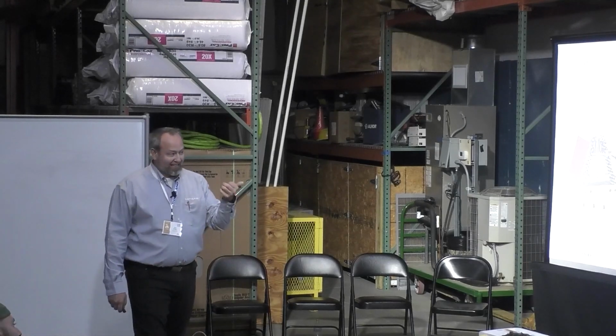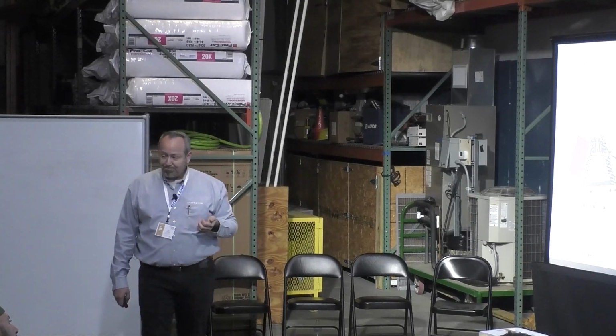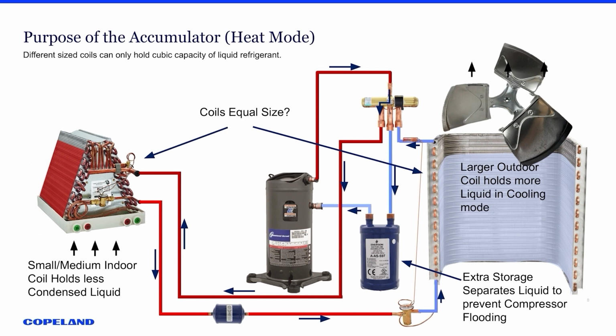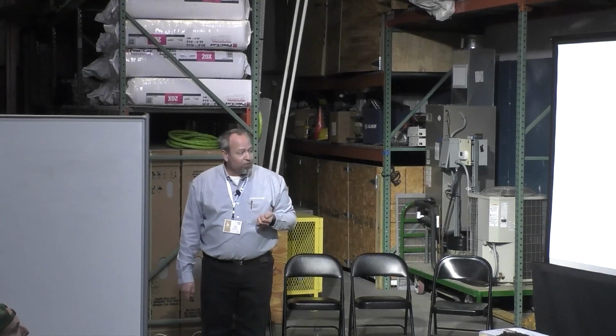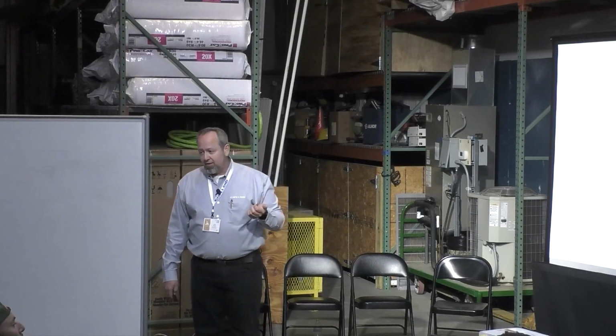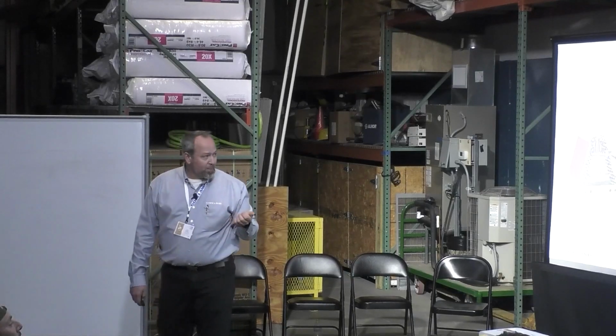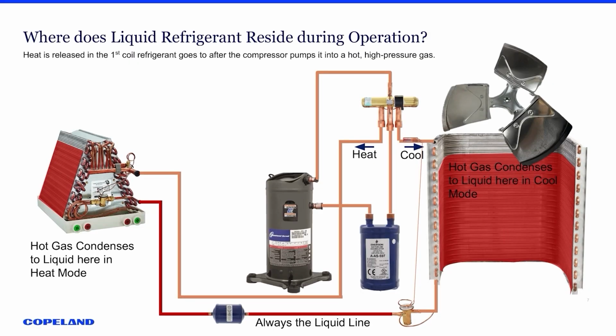One, that's needed in the heating cycle versus the cooling. And our next slides will kind of highlight that, and that is just simply understanding refrigerant storage and the accumulator, how that all works. Where does liquid go in the refrigeration cycle? Where does it reside? And we know we'll start in the outdoor unit, hot gas condenses to liquid in the cool mode. That's what we're used to.